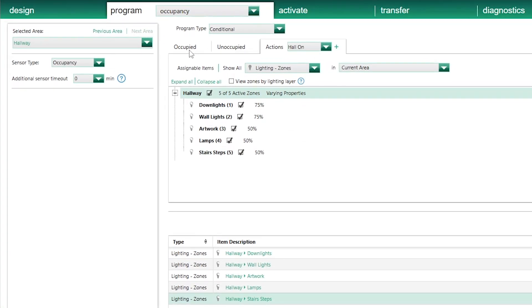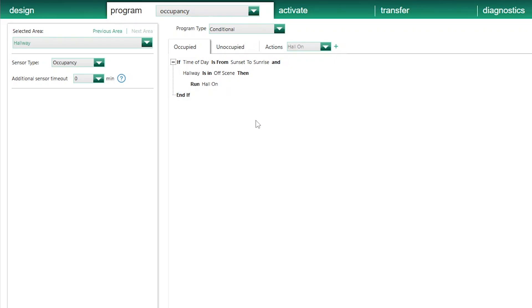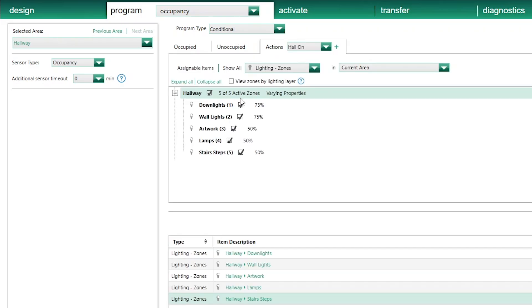Back on the Occupied tab, I can check that when my hallway is occupied, if it is night time and the hallway is off, I run the Hall On action. During daytime, nothing happens. And if it is night time but the hallway lights are already on to any level, nothing will happen either. When the hallway becomes unoccupied, I'll add another action — Hall Off — which will switch the hallway lights off. On the Unoccupied tab, I make sure the Hall Off action is selected and will run at any time of the day after a timeout of 10 minutes.